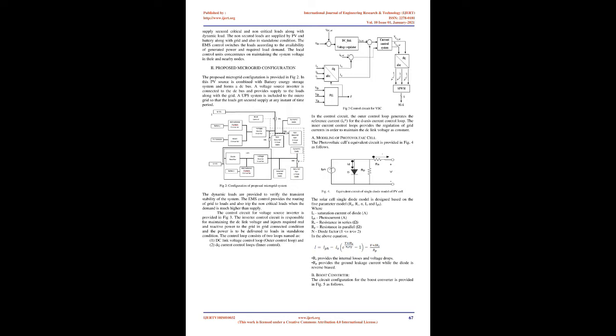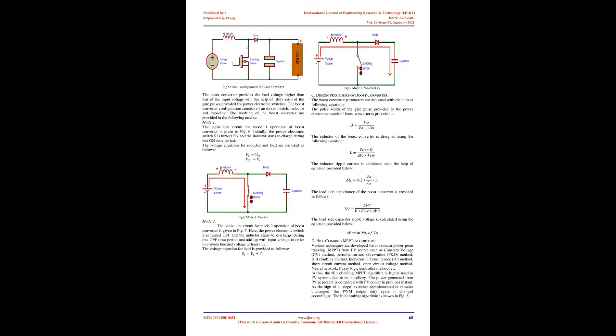The coupling of energy storage devices and distributed energy resources, DER, is achieved and tests are performed for various possible scenarios in 3. The active demand side management, ADSM, is done to increase the reliability of the grid system with the help of MPC, Model Predictive Controller, in 4, 5. The role of MLIs, multi-level inverters, in the microgrid is discussed along with improvement of modulation techniques. 6. A supervisory control is introduced along with local control such as modified hysteresis control and averaging of power with low-pass filters so that the hybrid power-sourced microgrid operates in different modes.